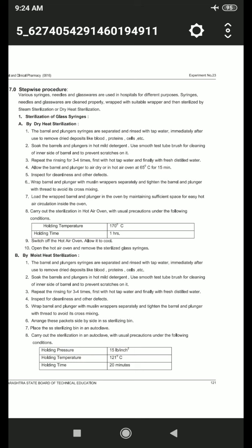Then the next step is to carry out the sterilization in the hot air oven with usual precautions under the following condition. First, holding temperature is 170 degrees Celsius and holding time is 1 hour. Then switch off the hot air oven and allow it to cool. Then open the hot air oven and remove the sterilized glass syringes. Okay, these are the steps for sterilization of the glass syringe by dry heat sterilization.